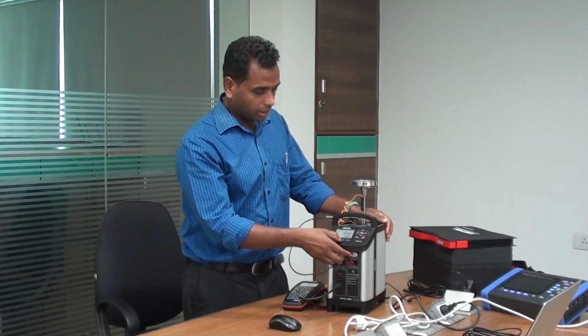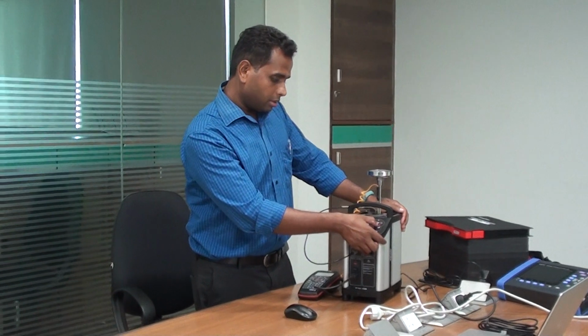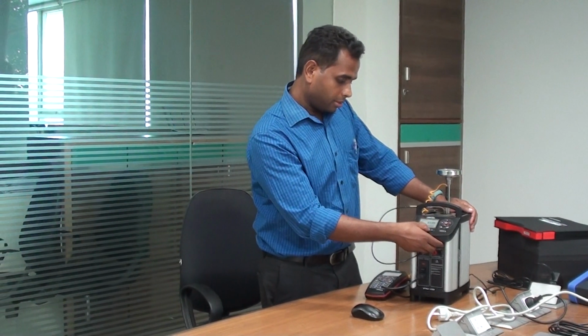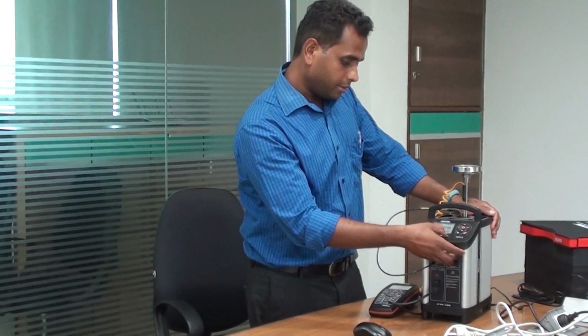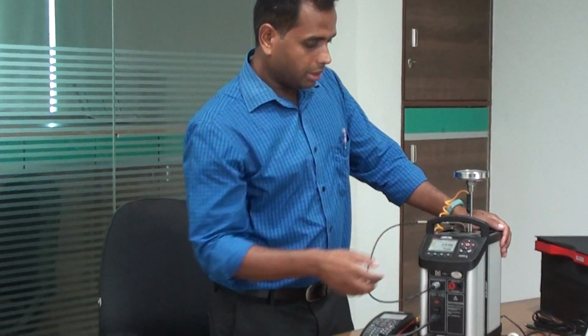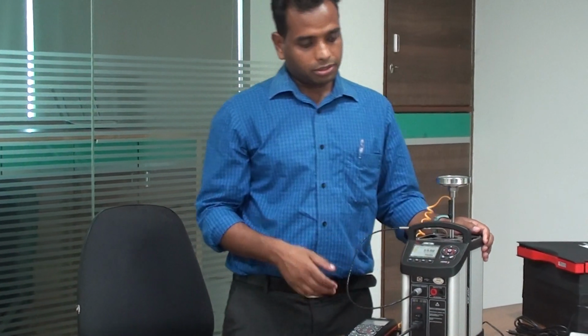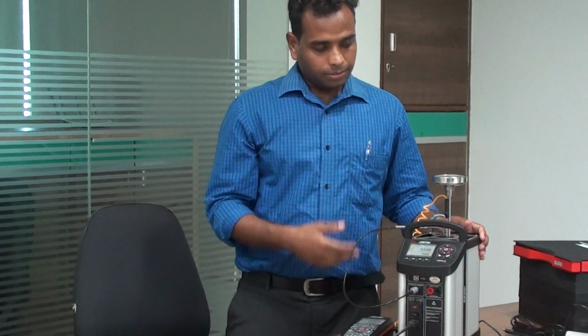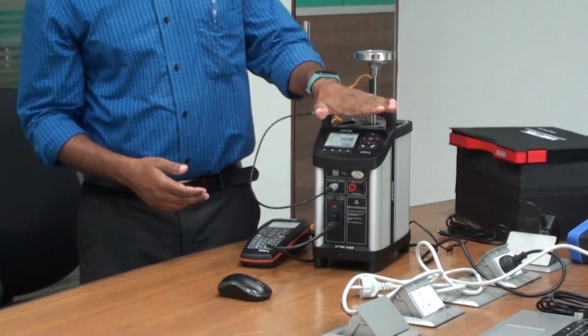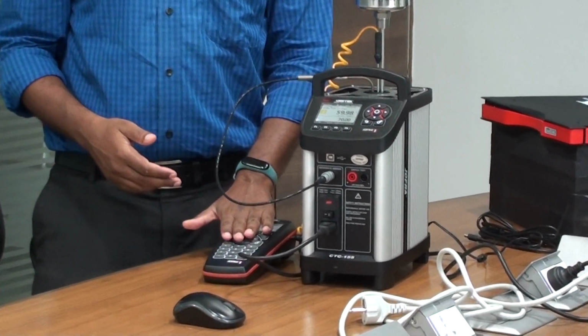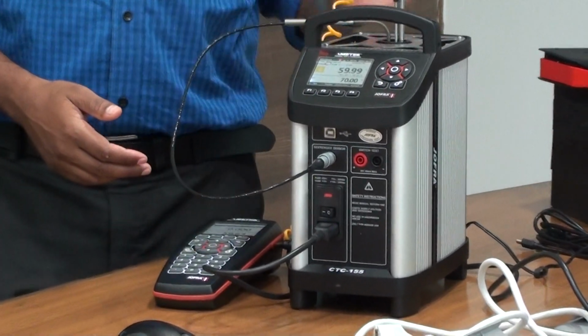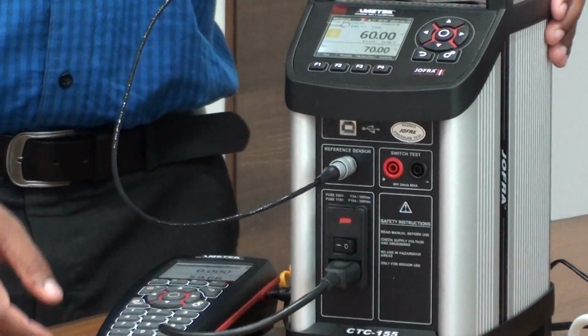So now we'll take another step. We'll increase the step. Now we'll put 70 degree. Now we'll increase the temperature. Again, it will take 1 minute to get stable. The same way we have to take the reading, master reading minus DUT, and that will be the error in the instrument.